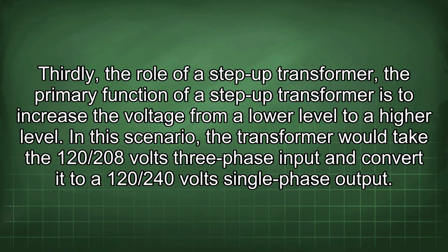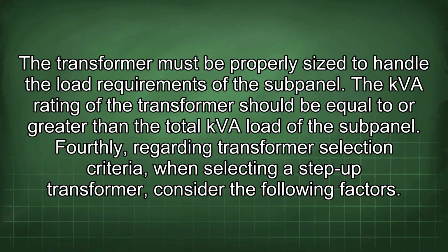Thirdly, the role of a step-up transformer. The primary function of a step-up transformer is to increase the voltage from a lower level to a higher level. In this scenario, the transformer would take the 120/208 volts three-phase input and convert it to a 120/240 volts single-phase output. The transformer must be properly sized to handle the load requirements of the subpanel. The kVA rating of the transformer should be equal to or greater than the total kVA load of the subpanel.